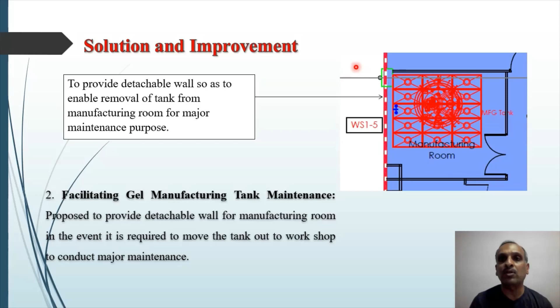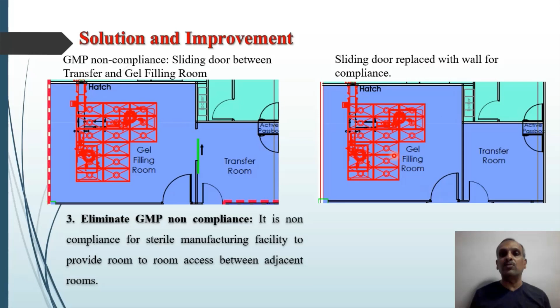Solution and improvement number 3 is related to regulatory GMP non-compliance, whereby a weakness observed in the proposed layout facilitates the transfer of primary packaging material from the transfer room directly to the gel filling room via a sliding door. This is not acceptable in GMP clean rooms. So the simple solution is to replace the sliding door with a panel wall, and let the transfer of primary packaging material happen via this hatch door into the corridor, and hatch door into the gel filling room.